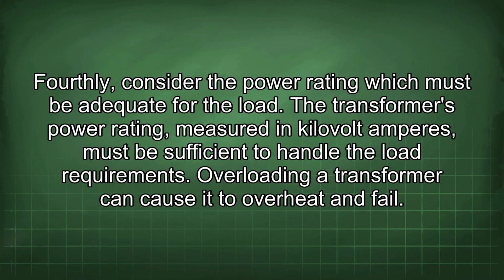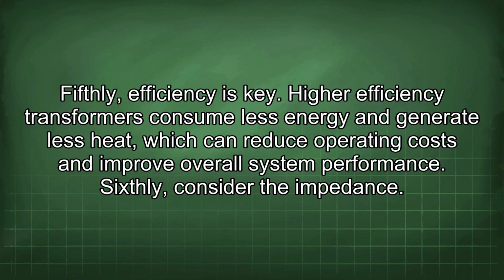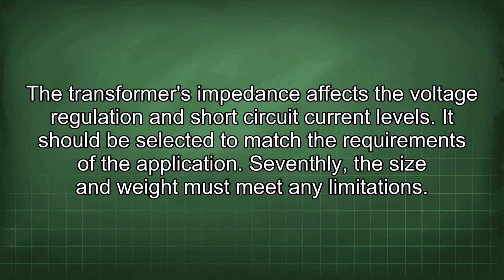Fourthly, consider the power rating, which must be adequate for the load. The transformer's power rating, measured in kilovolt amperes, must be sufficient to handle the load requirements. Overloading a transformer can cause it to overheat and fail. Fifthly, efficiency is key. Higher efficiency transformers consume less energy and generate less heat, which can reduce operating costs and improve overall system performance. Sixthly, consider the impedance. The transformer's impedance affects the voltage regulation and short-circuit current levels. It should be selected to match the requirements of the application.